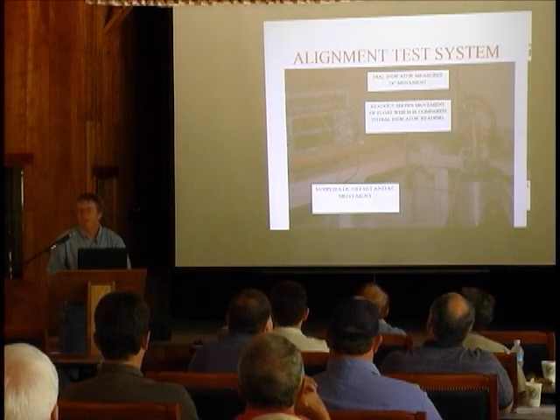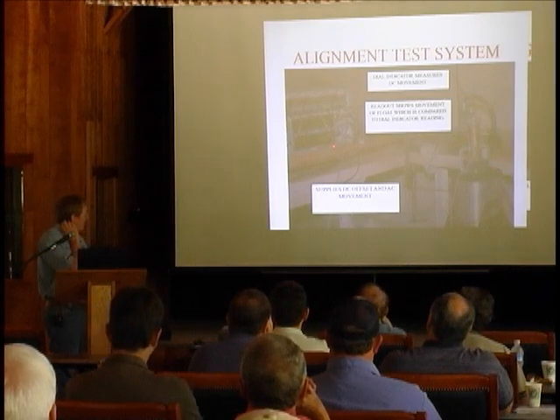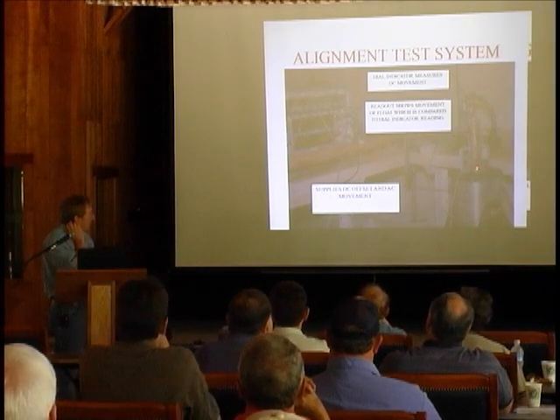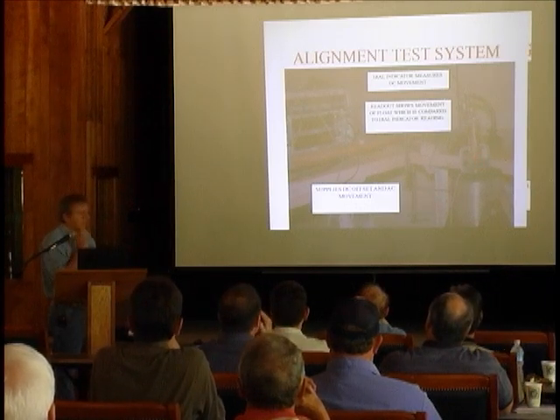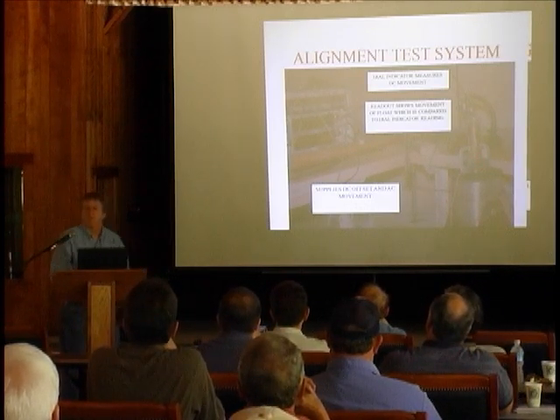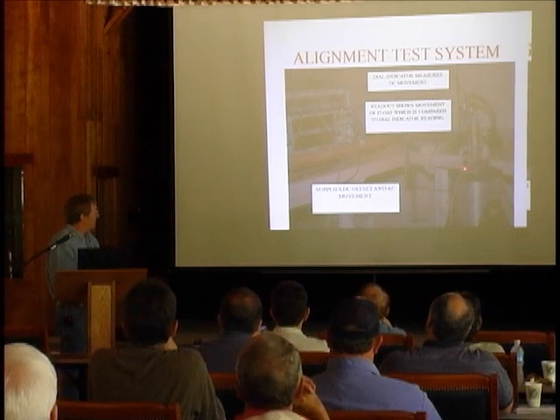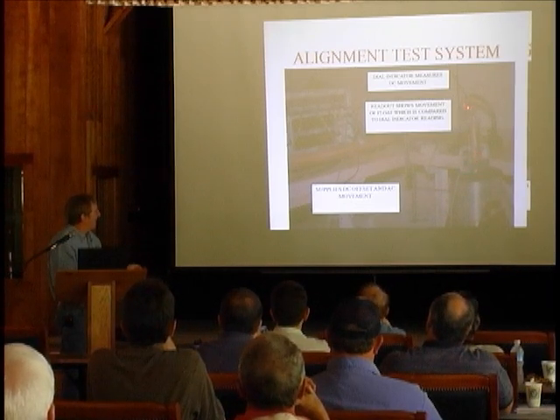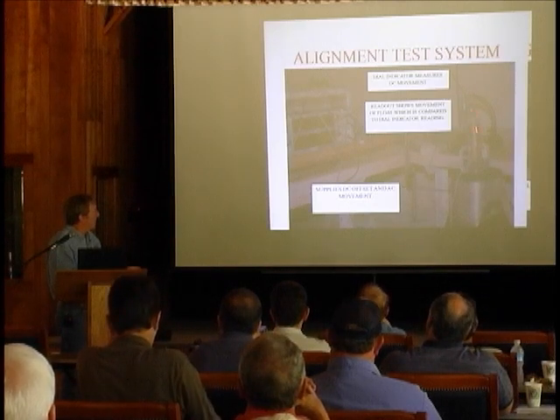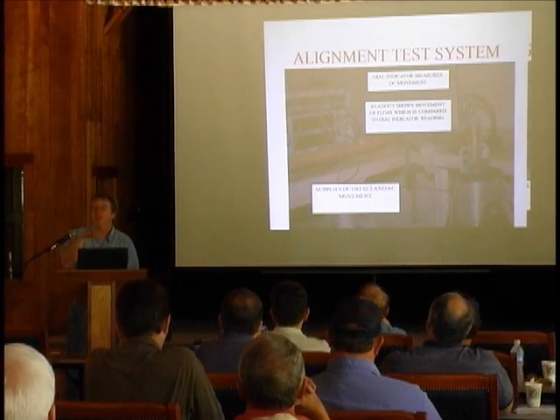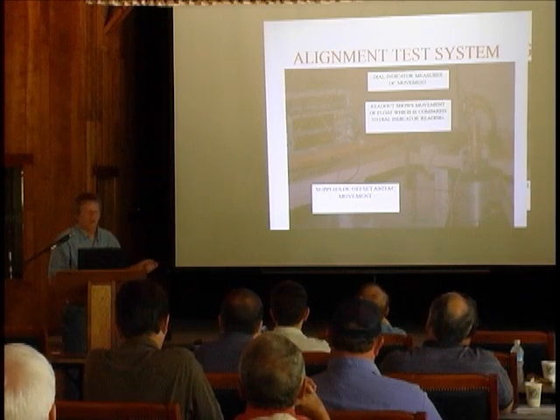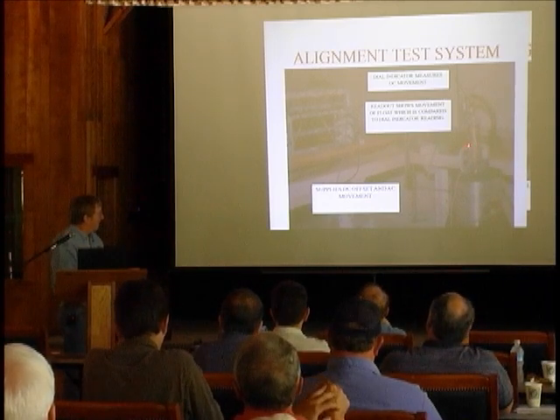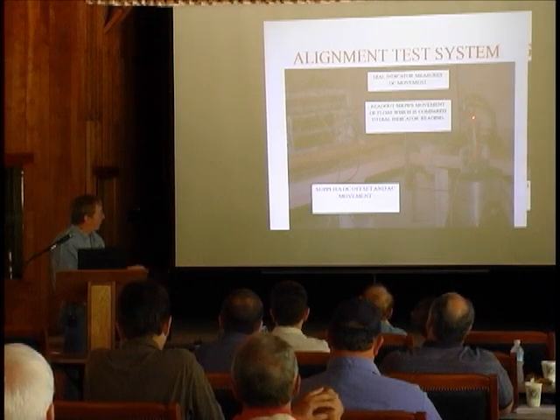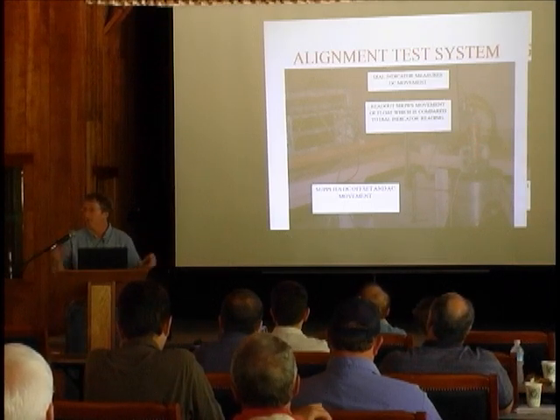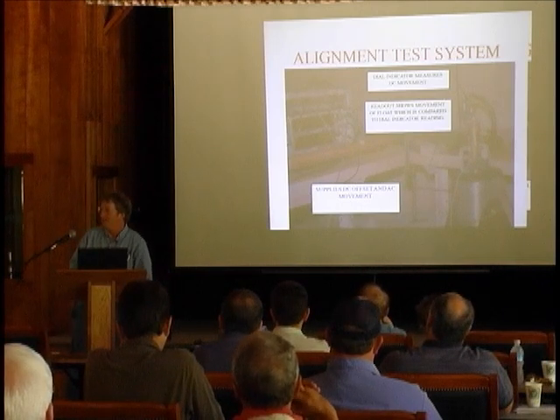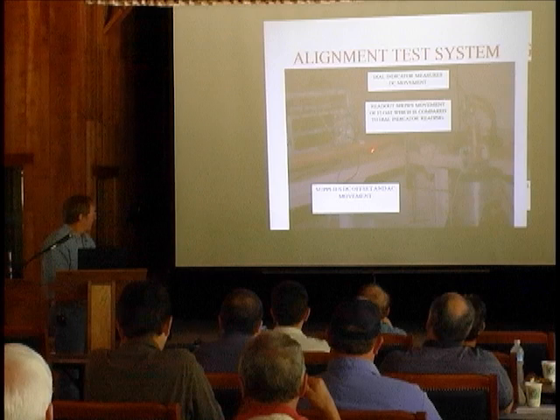The gap changes. So I tested this out in the lab. This is my lab setup. I had a shaker here. I put a 60 hertz signal on it, simulating a machine running 60 hertz. Then I throw in some DC, and I've got a dial indicator up here, and I throw in enough DC on my shaker to raise, say, 0.003 of an inch on the dial indicator. Then the fluid would flow out, the little float thing would drop, and the probe would measure the DC gap difference, and it worked great. The Canadians had an idea, and it worked good. I altered the idea a little bit.